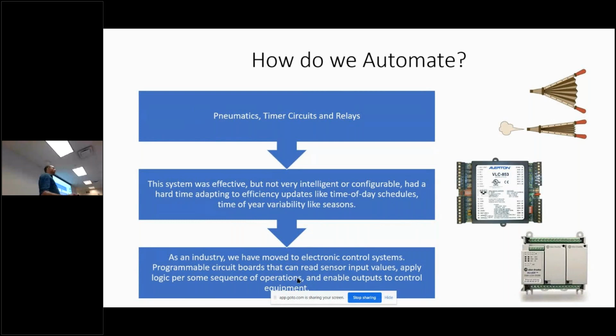So if we want to save energy and shut a building down at a particular time, pneumatic systems had a harder time and required much more manual control. As electronics and computers rose, the industry drifted toward electronic boards that could manage inputs and outputs and be configured to do exactly what we want. You'll come across two major types of electronic control in building automation: DDC, Direct Digital Control, and PLC, Programmable Logic Controller. DDC is primarily seen in commercial buildings, while PLC is primarily seen in industrial applications like wastewater treatment plants and power utilities.